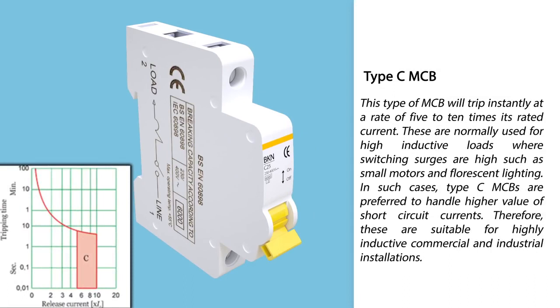Type C miniature circuit breaker will trip instantly at a rate of five to ten times its rated current. These are normally used for high inductive loads where switching surges are high, such as small motors and fluorescent lighting. In such cases, Type C is preferred to handle higher values of short circuit currents, and is therefore suitable for highly inductive commercial and industrial installations.